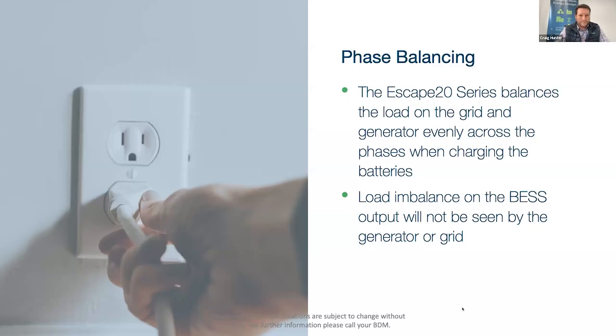The product allows 100% phase balancing, especially when you're looking at grids that are very small, or generators as well, when you're connected on the input side of a product. Because we're a true online UPS product, your load is totally isolated from the incoming AC source. So your load could have a 10 kilowatt load on one phase, 30 kilowatt load on another phase, and a 5 kilowatt load on the other phase. What the grid will see is 100% balanced load across each phase. So the system balances out, which is a benefit to utilities and a better benefit to the longevity of your generators.